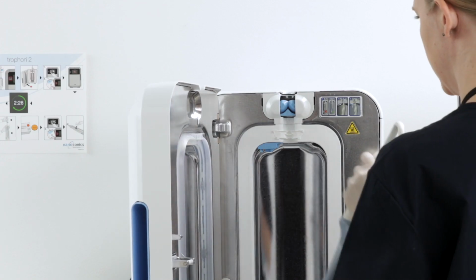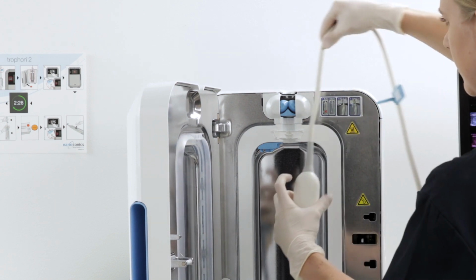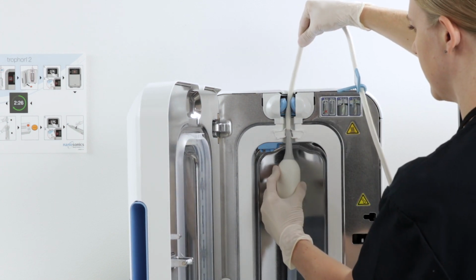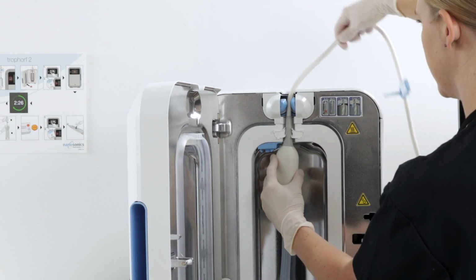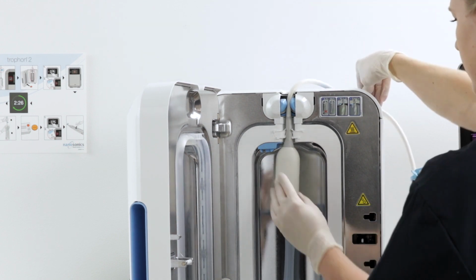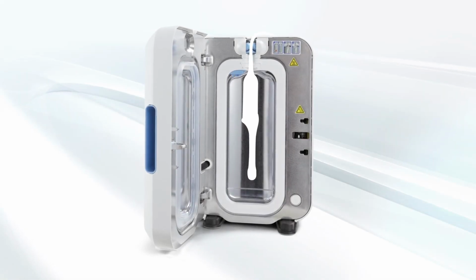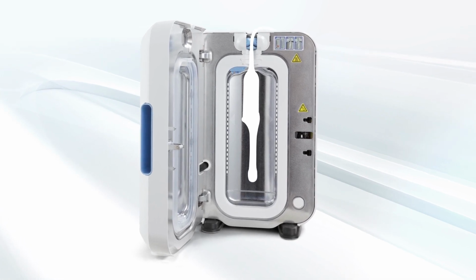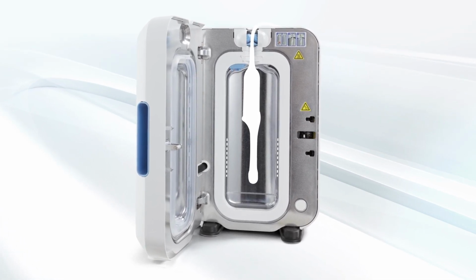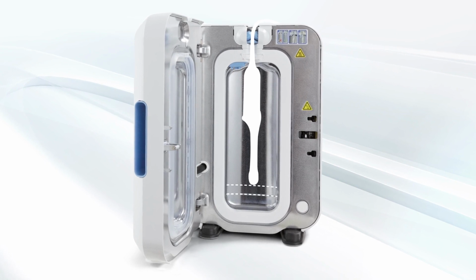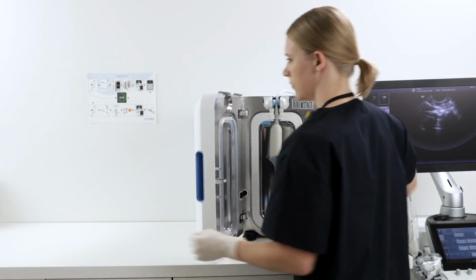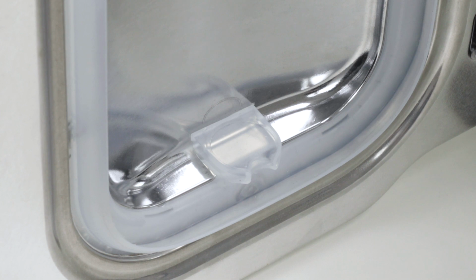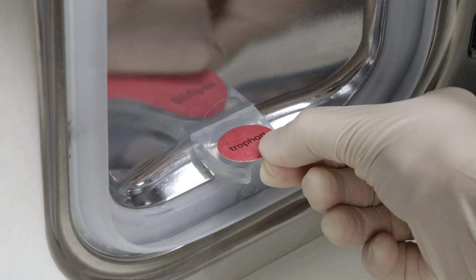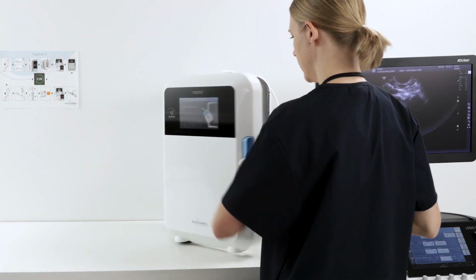Start by placing the probe cable strain relief below the cable clamp. Then, pull the probe up into the correct position. The cable clamp will secure the probe in place. Ensure the probe does not contact the chamber wall at any point, and that the tip of the probe is above the embossed line. Next, place a chemical indicator into the locator at the base of the chamber door, red side up. Close the chamber door.